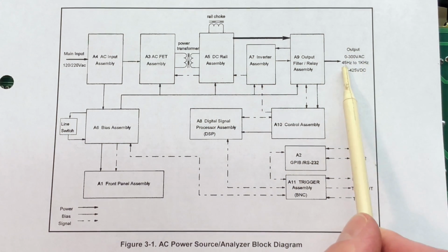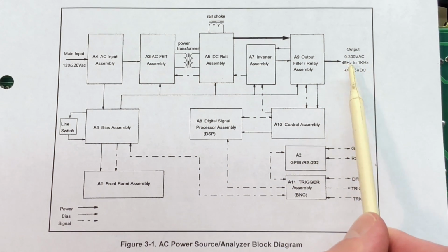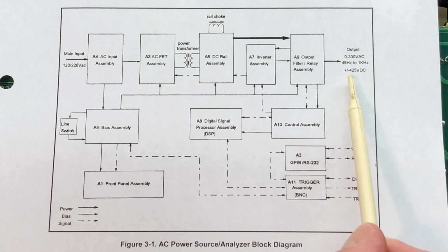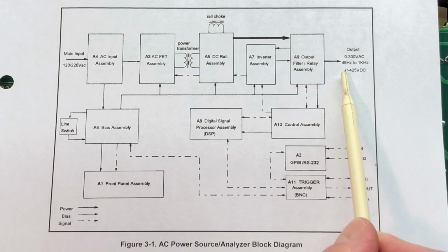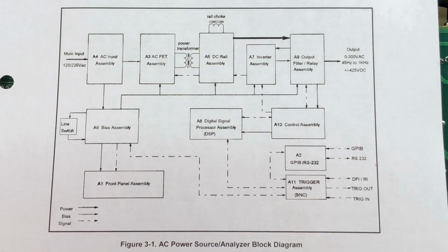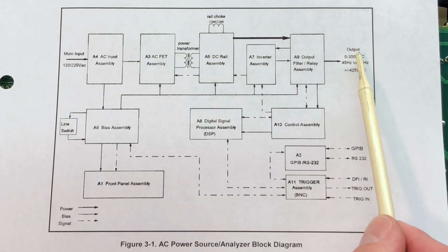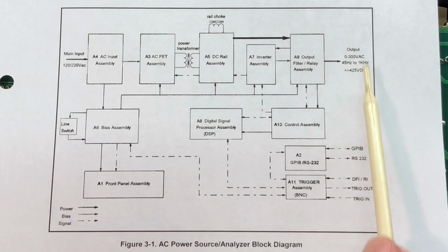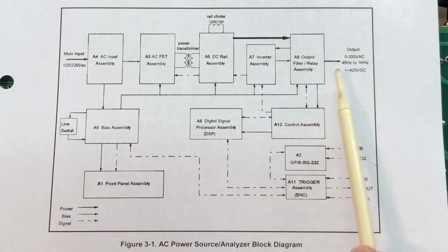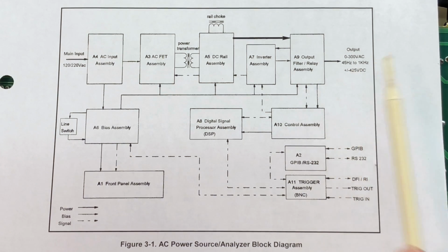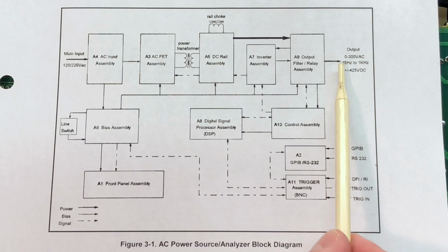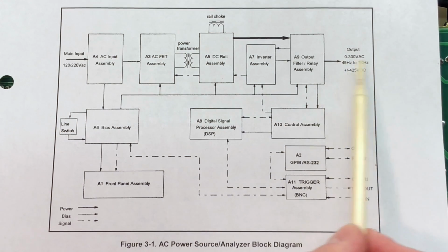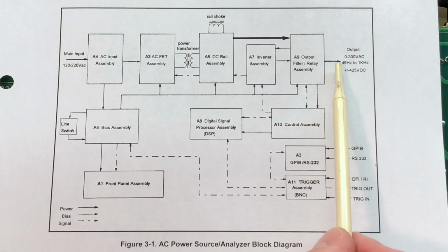Now, the output can actually extend below 45 hertz, and it can go all the way down to DC, and at DC the output can be fixed at up to plus or minus 425 volts DC. So basically you can have an AC output with a DC offset, or you can take the AC away and just have a steady DC output voltage. And you can vary the DC again from 0 up to 425 volts DC. So very flexible output, capable of quite a few different configurations. This does not have to be a sine wave. The output can be a square wave, it can be a clipped sine wave, it can be an arbitrary type signal, so very, very flexible in what it's able to develop.